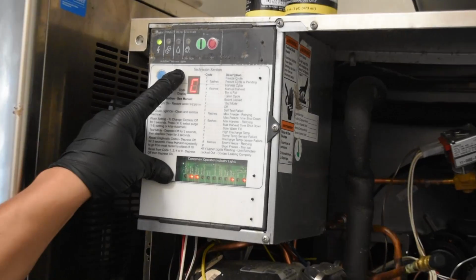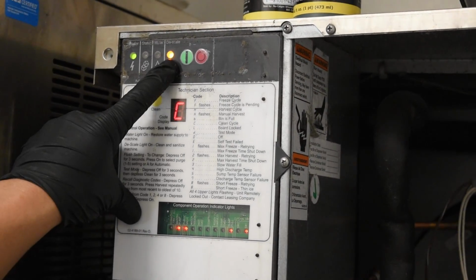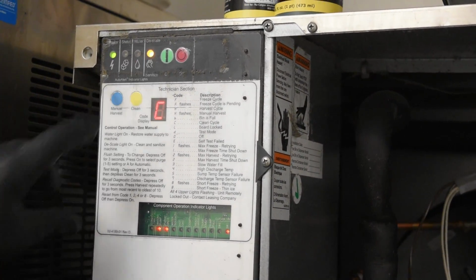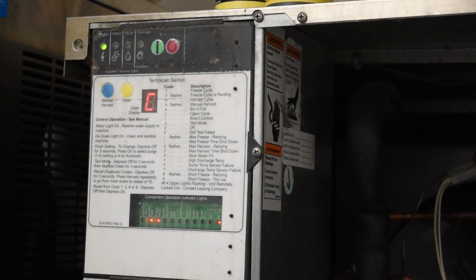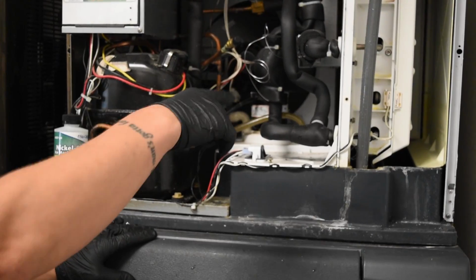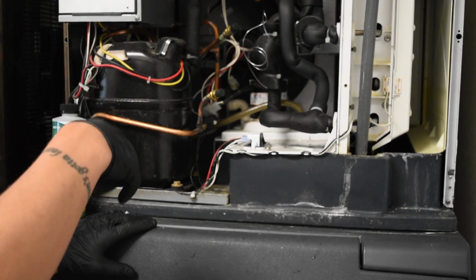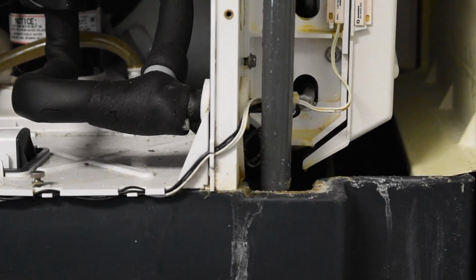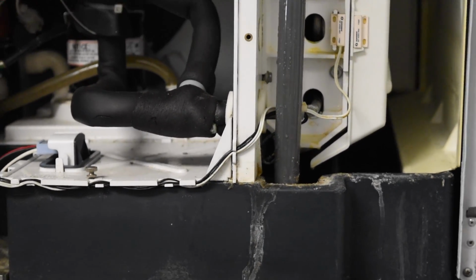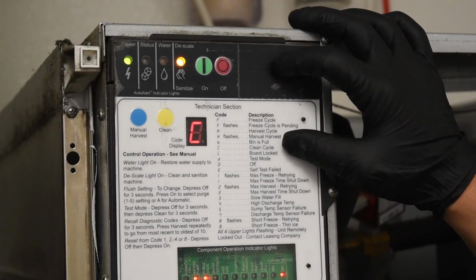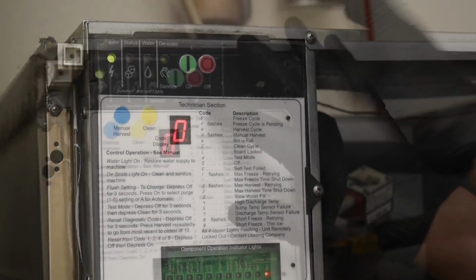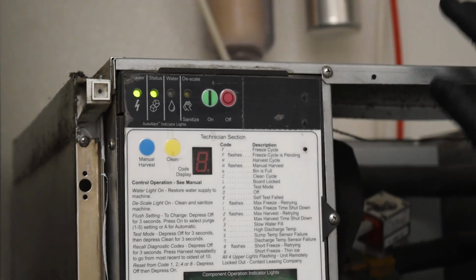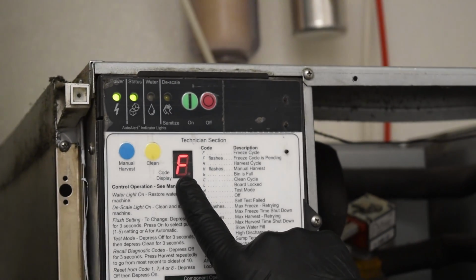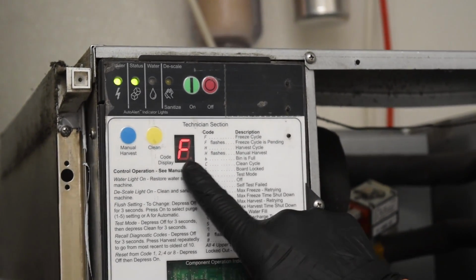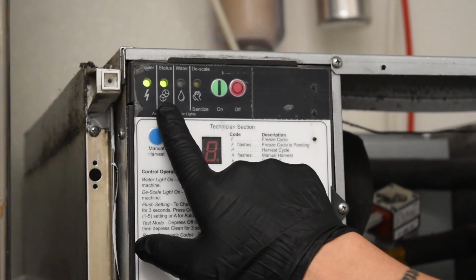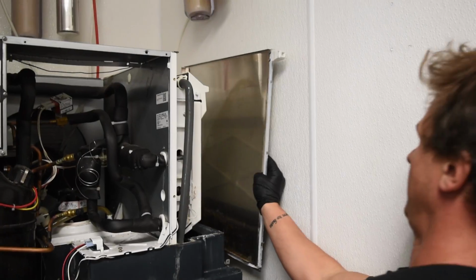After the sanitation cycle has run for 20 minutes, press and hold the yellow clean button until the descale sanitize button is solid. The machine will begin to purge itself by draining and filling with fresh water. Allow this purging cycle to continue for 20 minutes. Once the 20 minutes is complete, push the off button and then the on button. The letter F will appear, indicating the machine is back in freeze mode, along with the LED indicator light that the machine is ready to make ice.